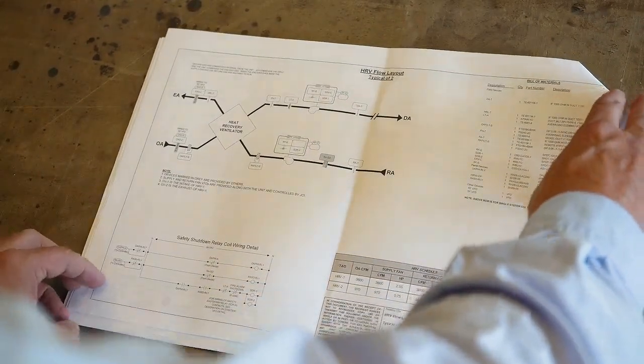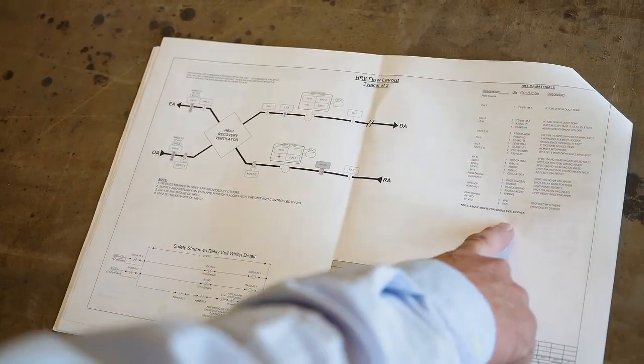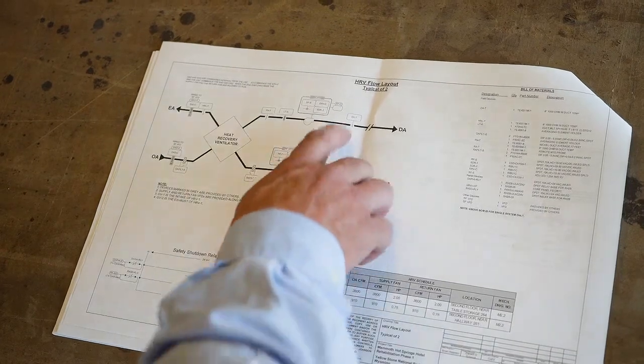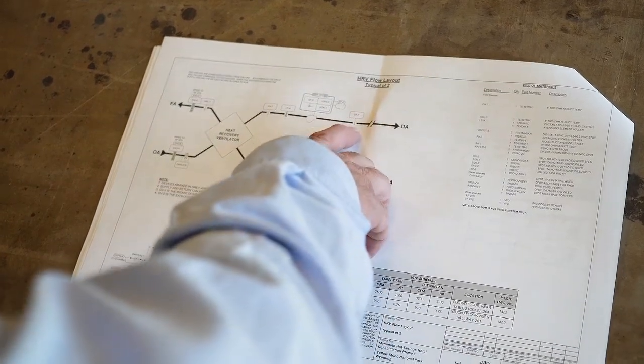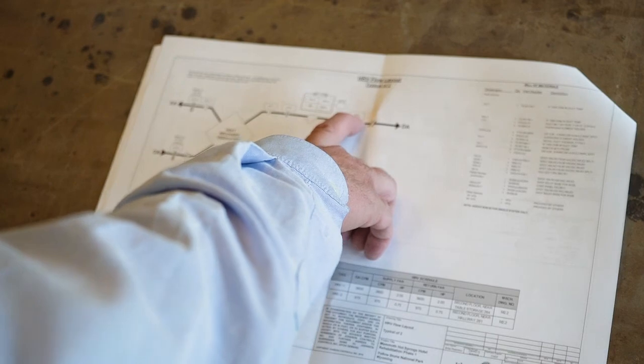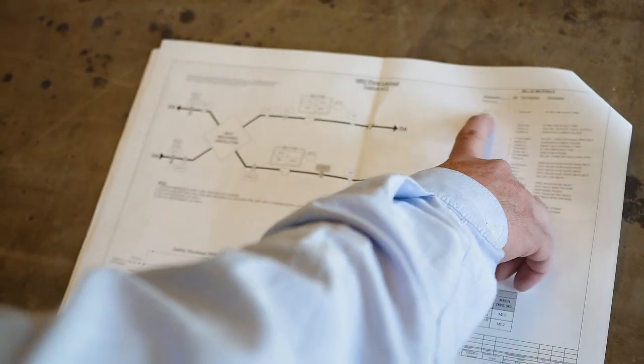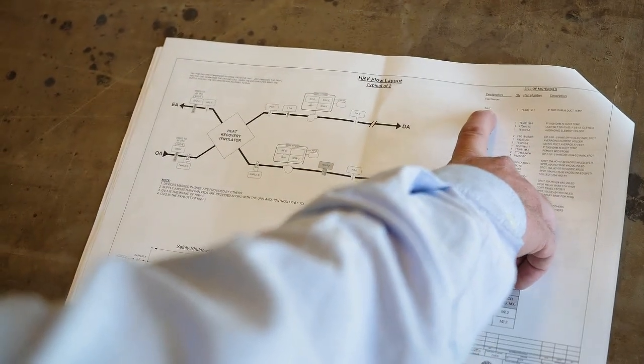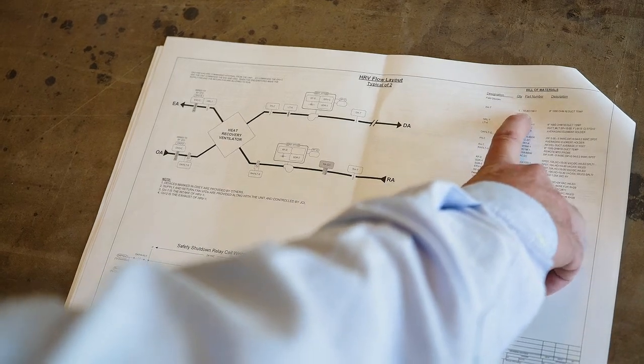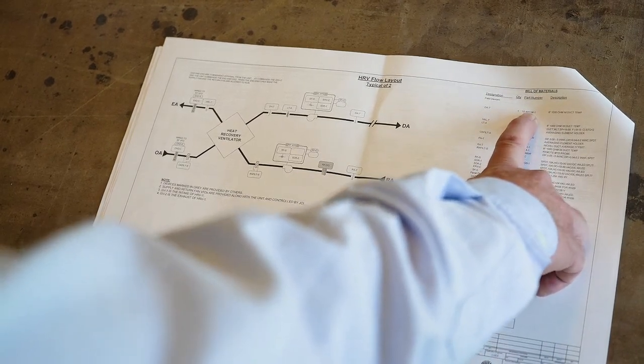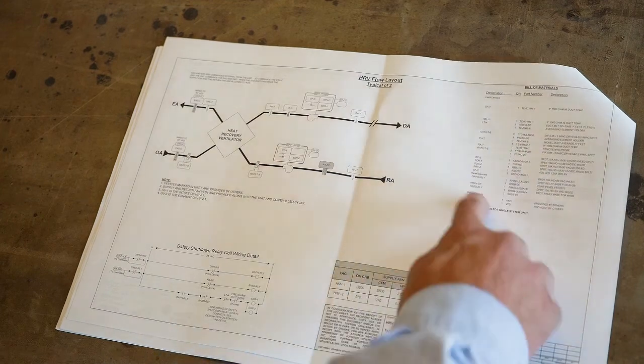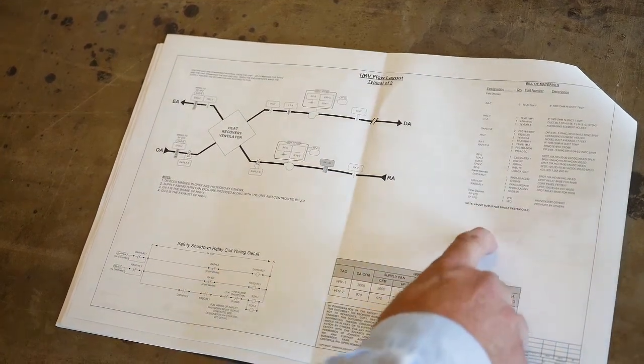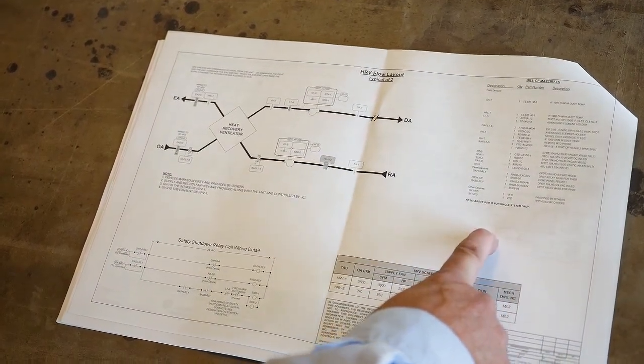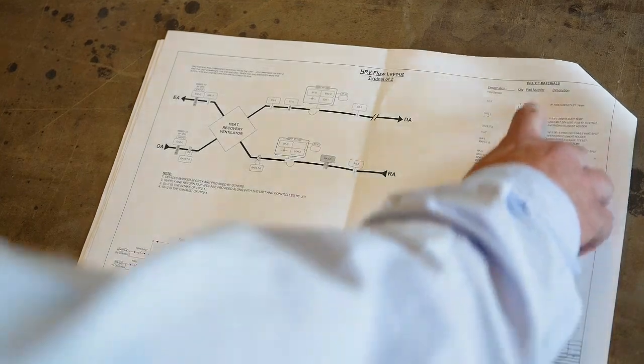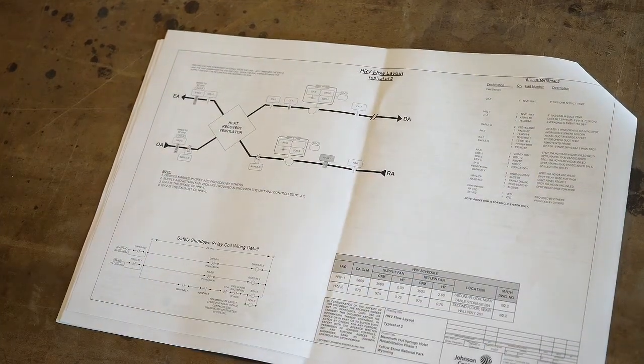Something else I wanted to point out to you is over here on the upper right-hand corner, we have this bill of materials. So for instance, if I pick this discharge air temperature, it's labeled DA-T, and you go over here under description, it's DA-T, and it tells you the quantity and the actual JCI part number. So you can actually get replacement parts right off this bill of material off these O&Ms. So this will list all of the parts on there.